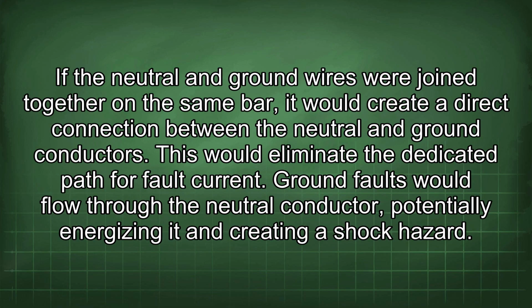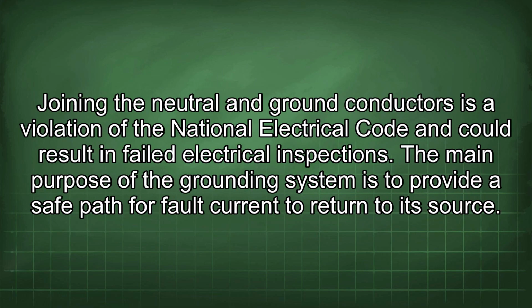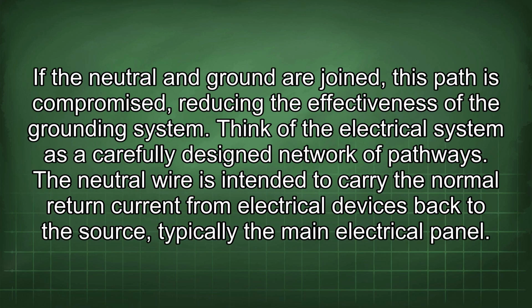If the neutral and ground wires were joined together on the same bar, it would create a direct connection between the neutral and ground conductors. This would eliminate the dedicated path for fault current. Ground faults would flow through the neutral conductor, potentially energizing it and creating a shock hazard. Joining the neutral and ground conductors is a violation of the National Electrical Code and could result in failed electrical inspections. The main purpose of the grounding system is to provide a safe path for fault current to return to its source. If the neutral and ground are joined, this path is compromised, reducing the effectiveness of the grounding system.